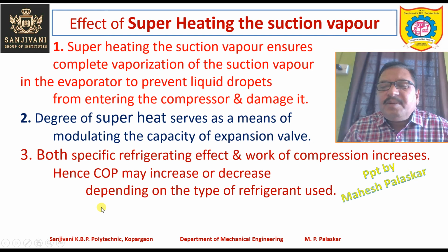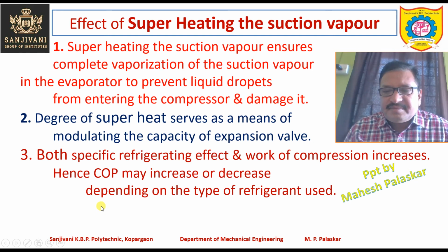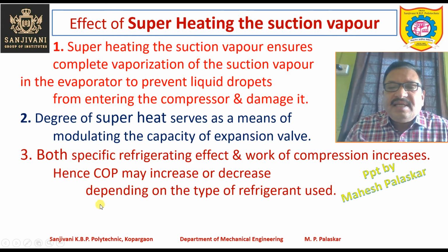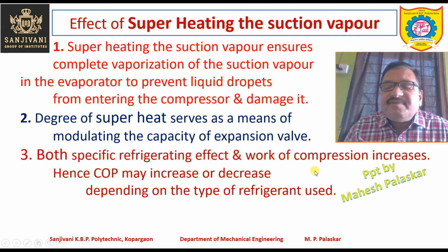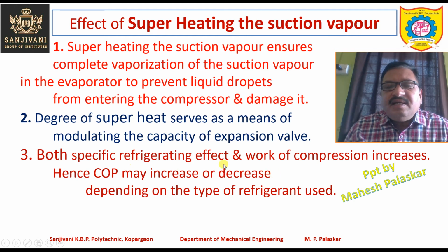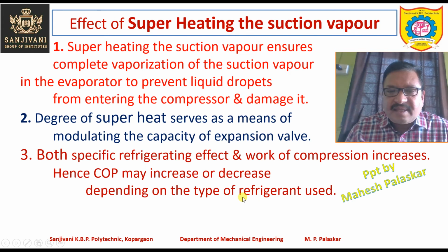So it depends upon which refrigerant we are using, and depending upon the refrigerant, the COP may increase or decrease. That depends upon the percentage increase in the refrigerating effect and the percentage increase in the work of compression, because both are increasing, and COP is the ratio of the specific refrigerating effect to the work of compression.